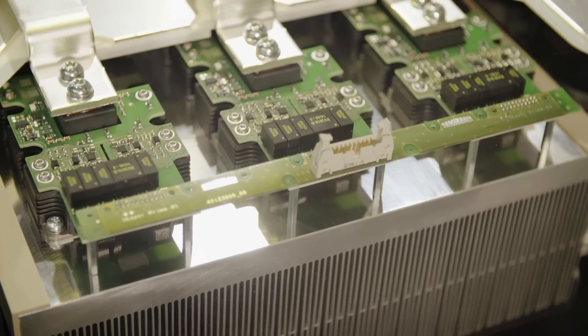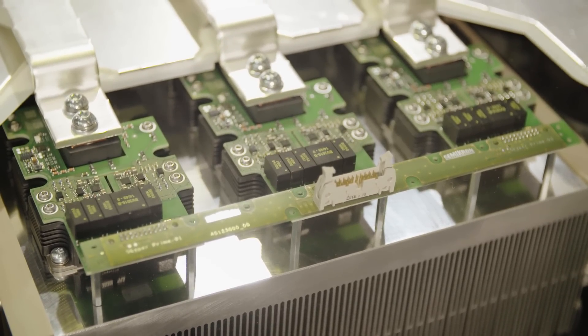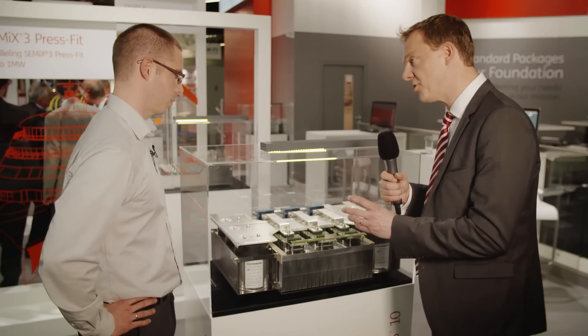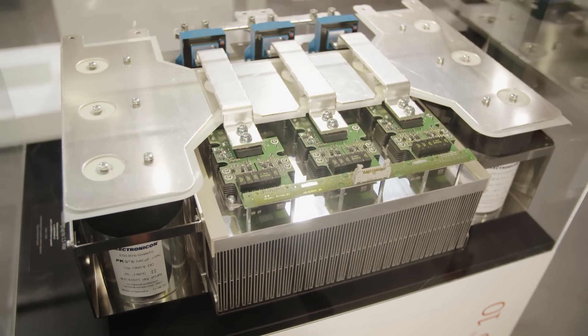So James, you can see here our reference design for high power — 1.5 megawatt based on our new Semitrans 10 and Skyper Prime. Most of our customers might have some challenges integrating our components in the best way, and that's our support for them, showing how to realize it in an optimized way. This is really just a demonstrator, this is not a product from Semikron. Exactly — we just show how it might be implemented in an optimized way, but it's not a qualified product or a qualified stack, it's just a guideline for the customer.